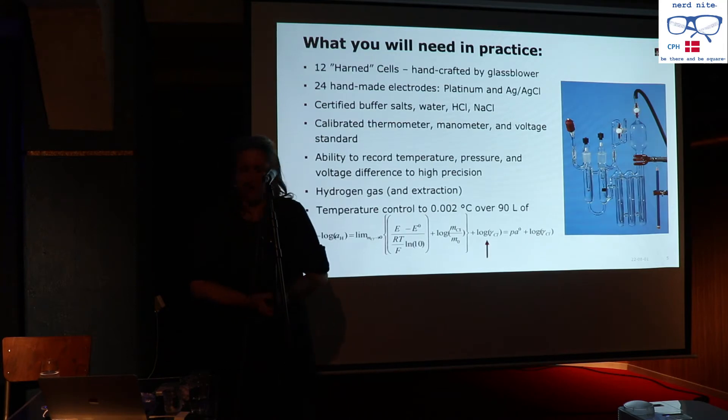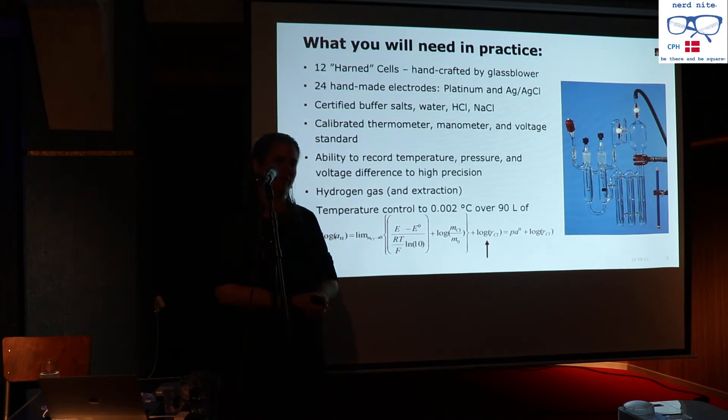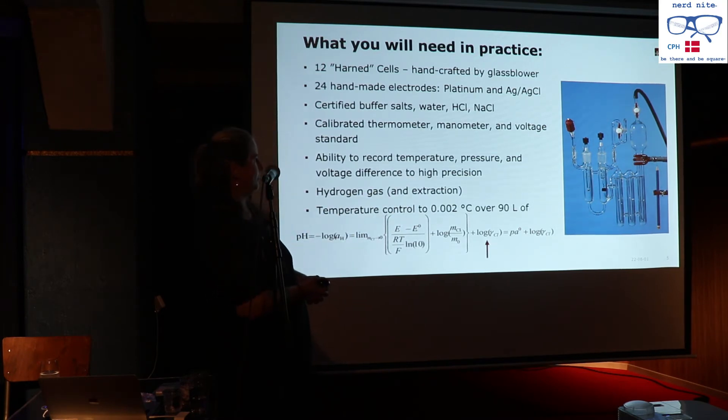This is what happens at the Danish Metrology Institute. You take 12 Harned cells that were made by a scientific glassblower who has unfortunately passed, and you fill them with very precisely made components. You need 24 handmade platinum and silver–silver chloride electrodes — you can't buy them, you have to make them. You need certified buffer salts that cost a lot of money.